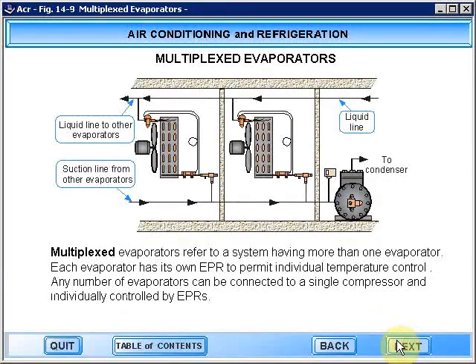Multiplexed evaporators refer to a system having more than one evaporator. Each evaporator has its own EPR to permit individual temperature control. Any number of evaporators can be connected to a single compressor and individually controlled by EPRs.